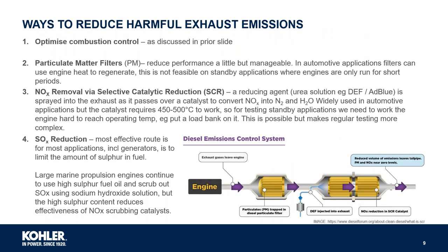So what ways are there to reduce harmful exhaust emissions? We can optimize combustion control, but as discussed, that has trade-offs, so it's limited in what it can achieve. To reduce particulates, we can fit filters, which reduce performance a little but is manageable. In automotive applications, filters can use engine heat to regenerate, but this isn't feasible in standby generators when engines only run for short periods.